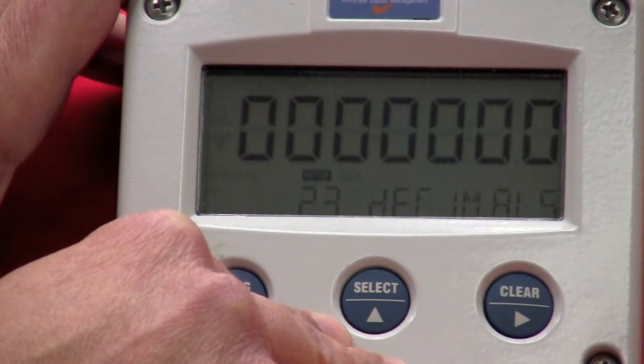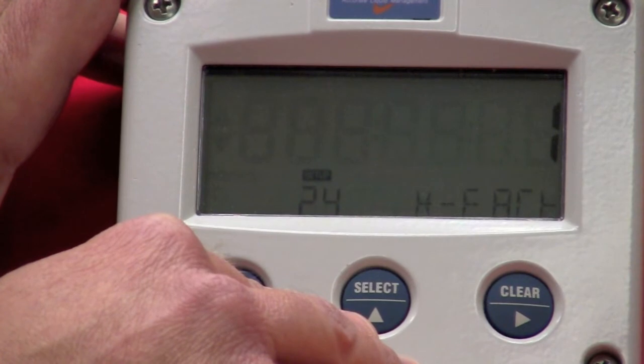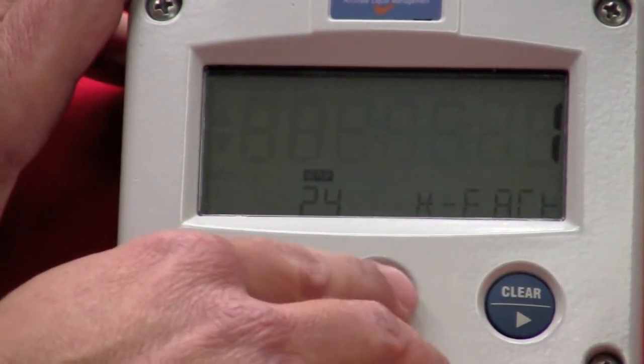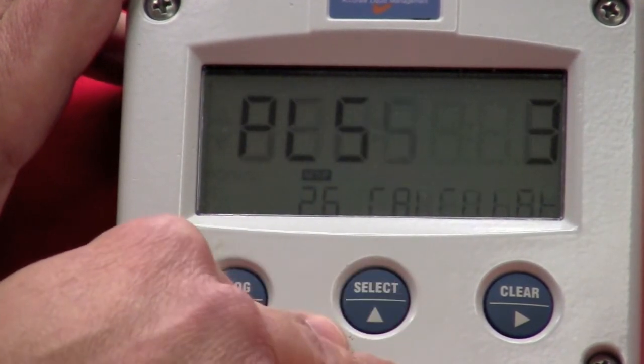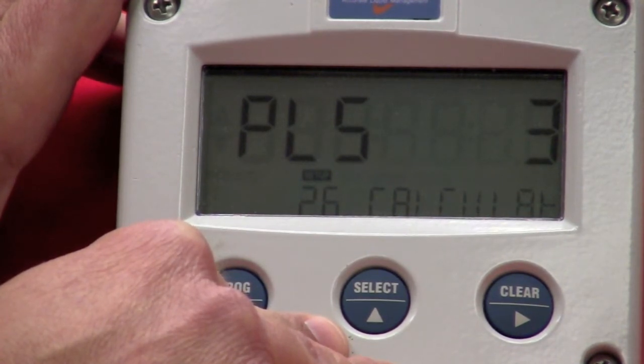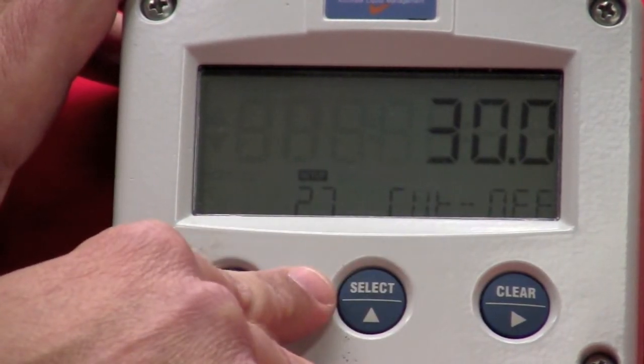Next would be your decimal point for your flow rate. Your K-Factor for your flow rate. Again, this is set at 1 for your demo. That way, every click registers as a pulse. Decimal point for your K-Factor. Calculate. Now, this is basically a filtering option that you have available with the unit. Ours is set for 3. I'll leave it that way.